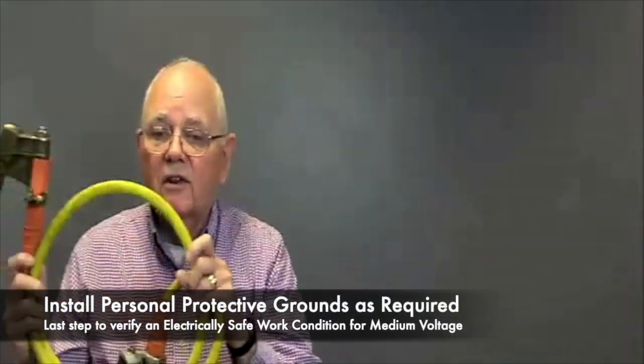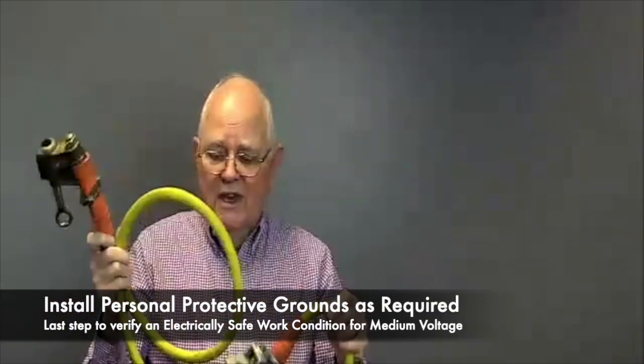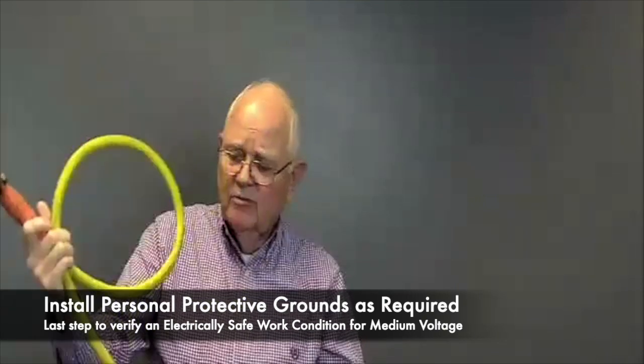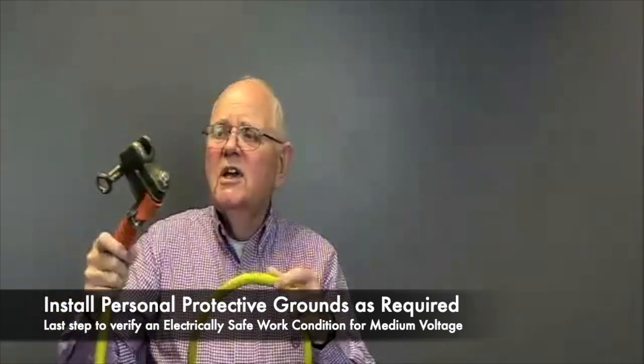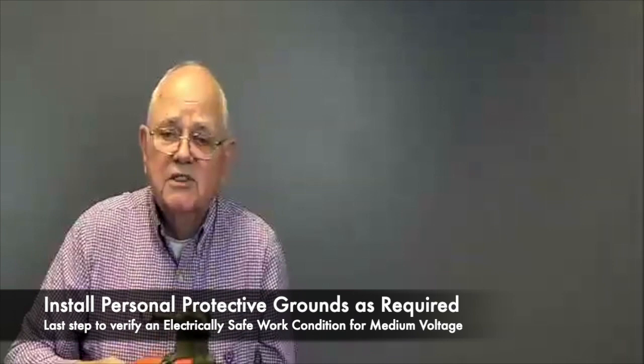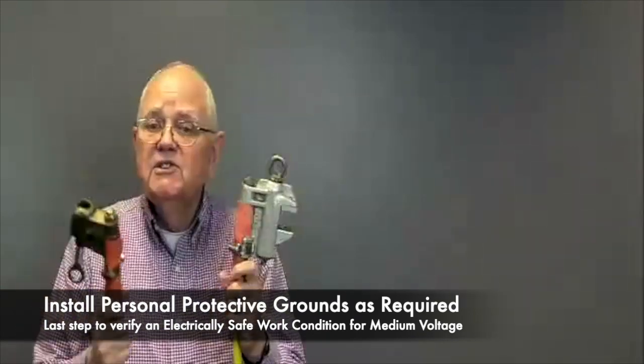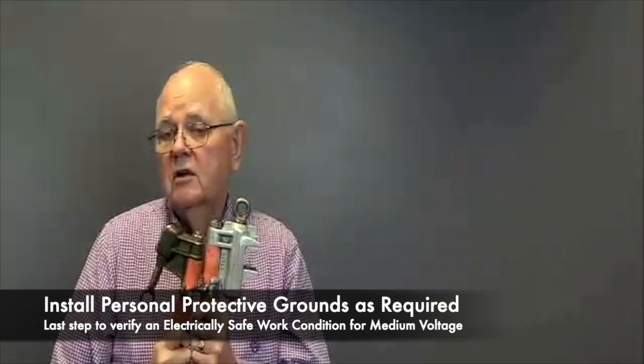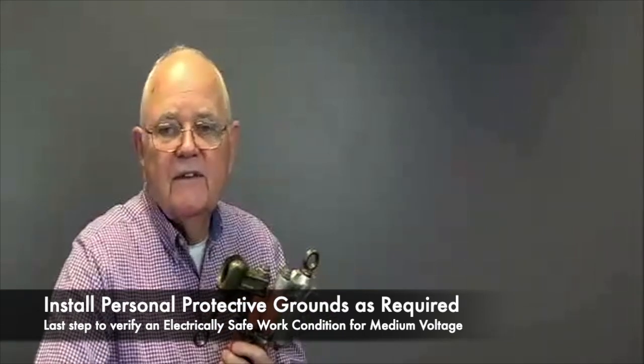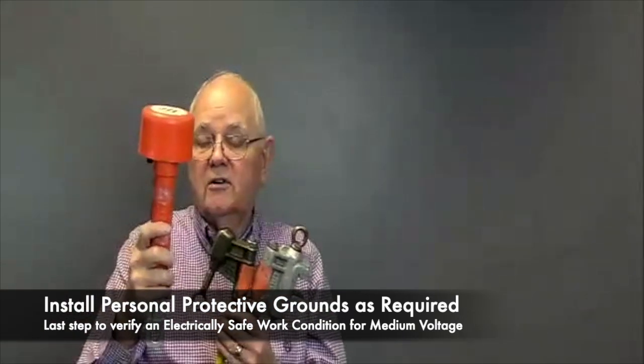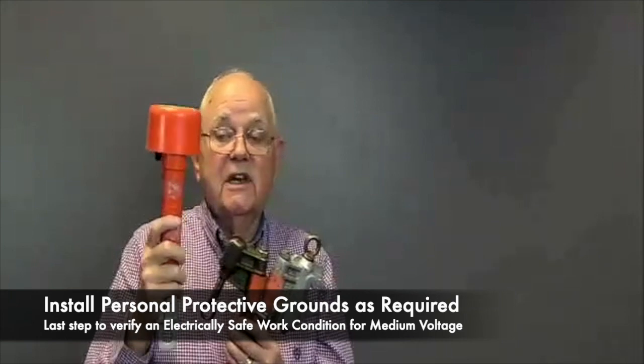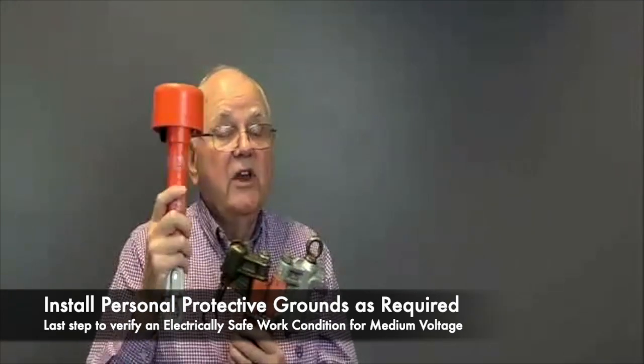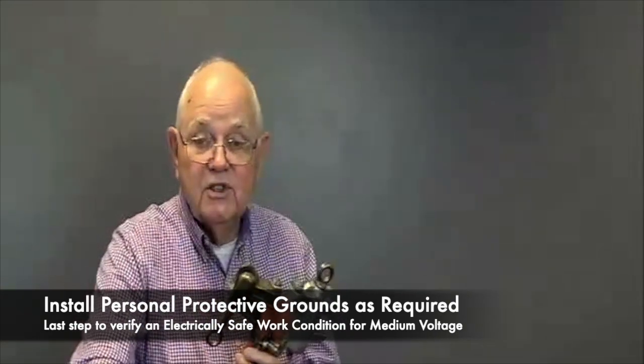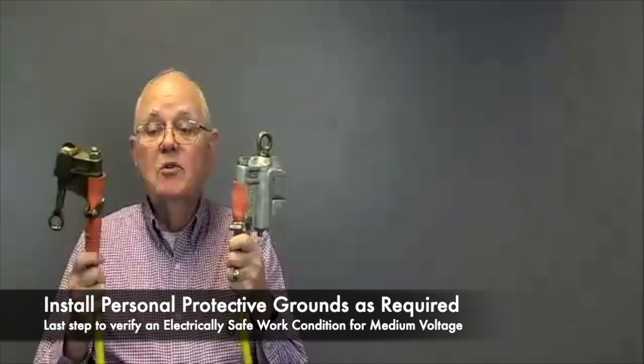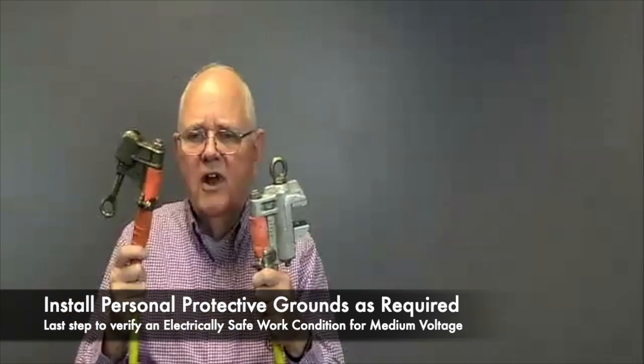I'm going to have to install some personal protective grounds, okay? And these are kind of big and heavy and clumsy. They're going to be a minimum of 2/0 cables, but they have clamps on them that are going to assist me. Now, this is still category 4 work. Just because I've verified the absence of voltage with a voltage detector doesn't mean I'm ready to take off my PPE yet. Not until I've installed, or as we say, hung our personal protective grounds, temporary grounds then.